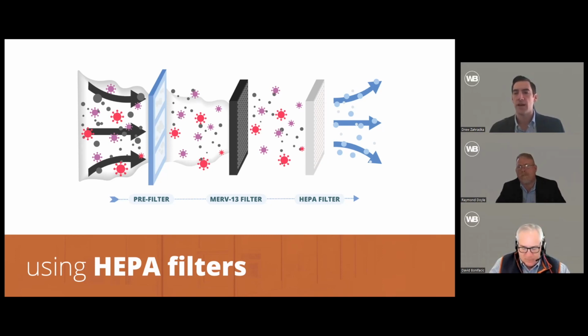But then in terms of sediment and dust, that's where you've got your pre-filter to pick up the bigger pieces, and then down to the HEPA filter to get the finer molecules and particles within the airstream. So you mentioned something that was interesting: recirc versus 100% outside air. How do you determine when you can just recirc and when you can take from the 100% outside air?